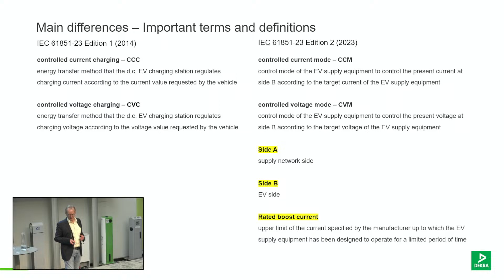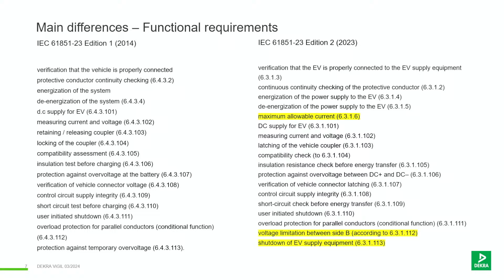When we look at functional requirements, they mainly remain identical. However, there are 3 requirements which have been added: maximum allowable current, voltage limitation at side B, and shutdown of the EV supply equipment - meaning normal shutdown or emergency shutdown.